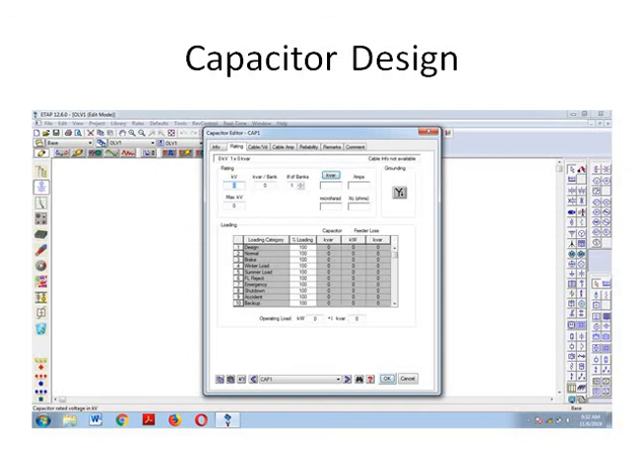So making use of a software gives a clear indication to the power system engineer of the conditions, like making use of a series capacitor will definitely improve the loading capacity. The shunt capacitor is going to improve the power factor of the system, but it is also important to maintain the voltage in the permissible limits as per the international standards. So the importance of power factor governs the relation with the power quality.